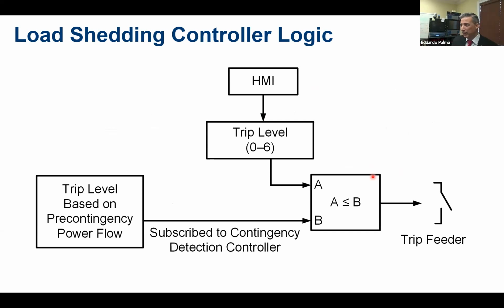This is complementary to what I've said before, and it's just a way of looking at the logic of how to do load shedding. Basically, there is a trip level or threshold of when we want to open the loads or disconnect the loads based on a pre-contingency power flow. And this goes into a logic gate, which is a comparison of whether A is less than or equal to B. A is the different trip levels that are available to operators.